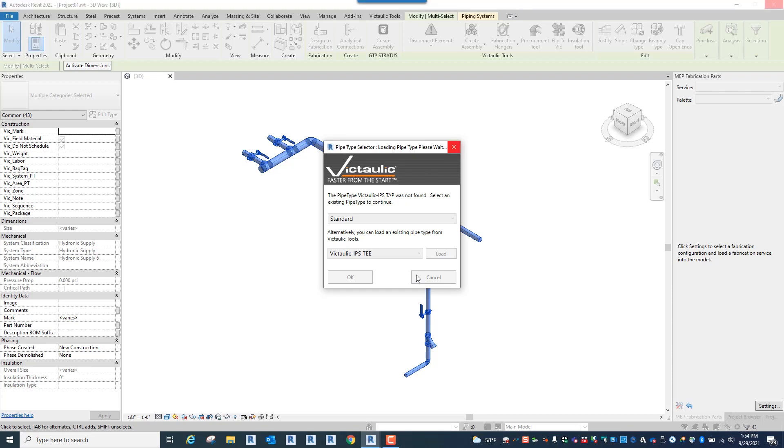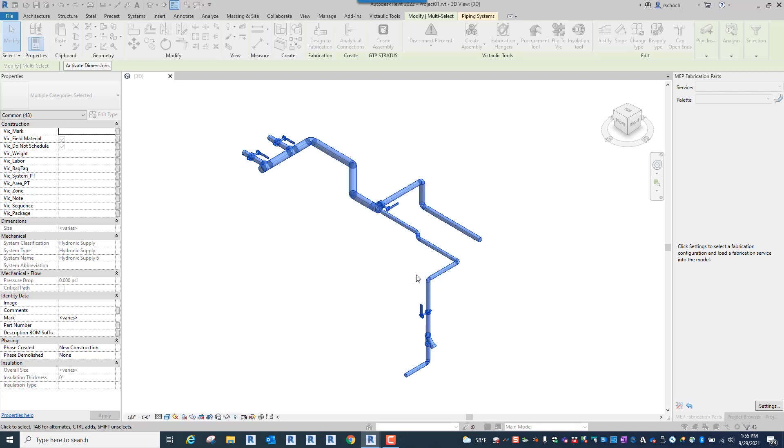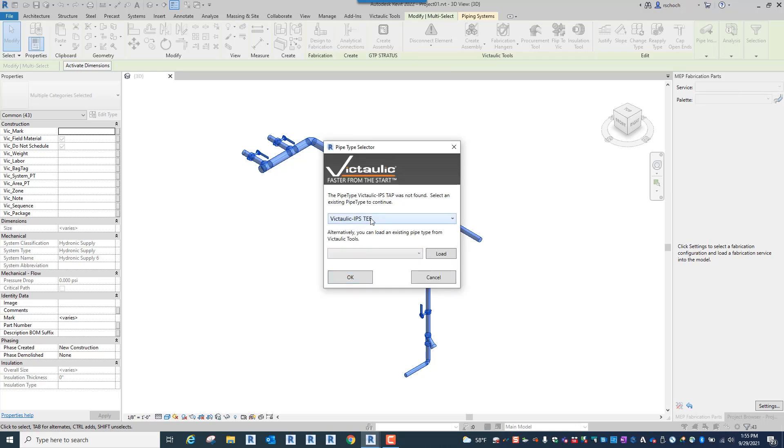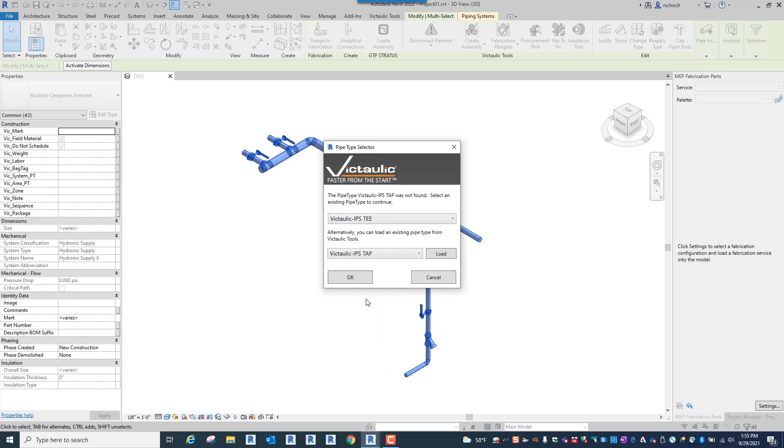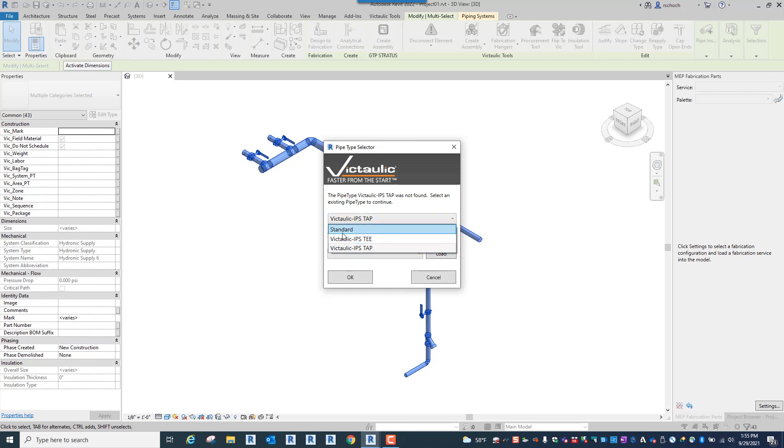If there's families in this project that are within that pipe type it uses those families for that pipe type. It doesn't load additional families in the project and it doesn't rename the content either. So if you've copied pipe from one project to the other and maybe there was already piping that was similar of the same pipe type in there, you'll notice that sometimes your pipe types get messed up or in your project browser you'll see a lot of additional families that really don't belong. So you can see in here I loaded the IPS TEE pipe type. I'll do the same thing and I'll load the IPS tap pipe type. So just that easy in the project I loaded two pipe types.